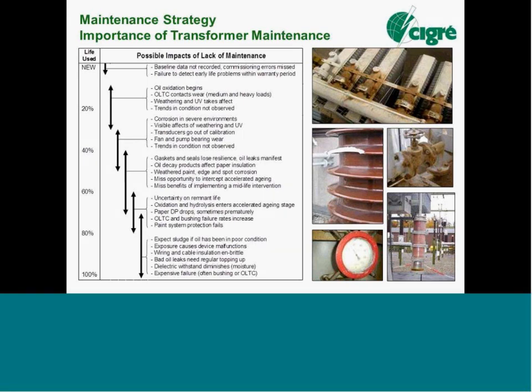What could happen? Down the left-hand side you see the life cycle for the transformer, from new to 100% of its life used. And typically we see these sorts of issues listed in the main box in the centre that can develop and degrade in the transformer. Some of these things are, of course, external, like paint, system corrosion, weathering, affected cabling, UV. Okay, I'll continue on.